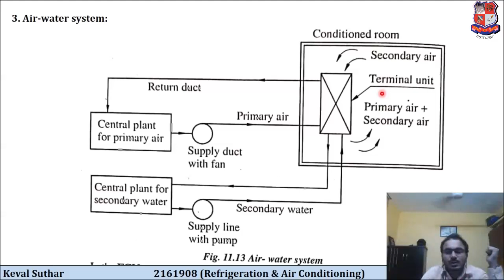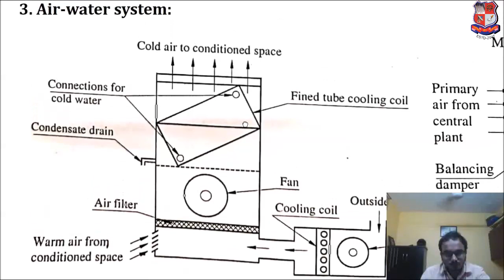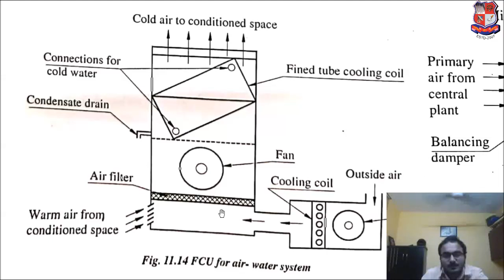Now we will discuss the terminal units for the air water system. There are two types. First is the FCU, that is fan coil unit, which is very similar to our previous FCU that was for the all water system. Let us focus on this FCU. Here the warm air is coming from the conditioned space through this passage, and the top part is very similar: we are having an air filter, then a fan. This is the cooling coil in which the cold water connection is there. Here the heat transfer will take place, this warm air will get cooled down, and then it goes into the conditioned space, and here the condensate drain is there. The only additional thing is that we are also using outside air into this fan, and then it is passing through this cooling coil. So this cold air is also doing the task of cooling. So this is about the FCU for the air water system.